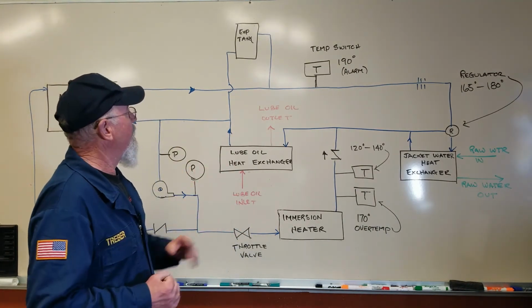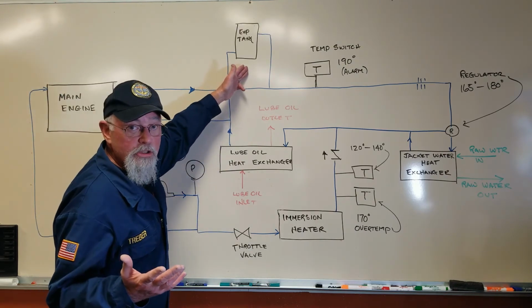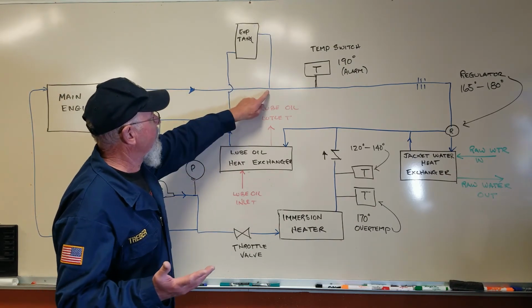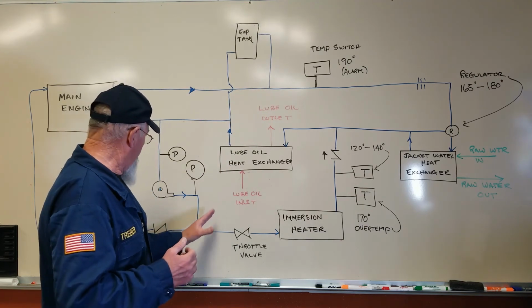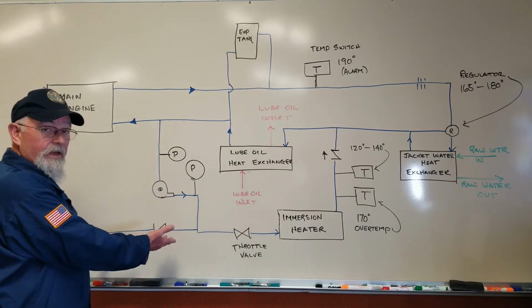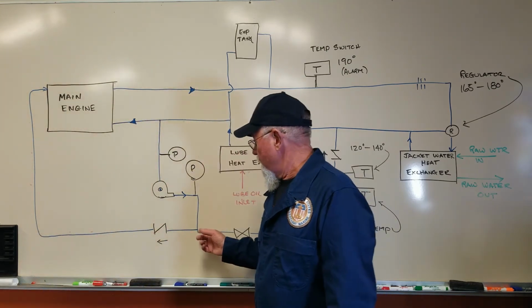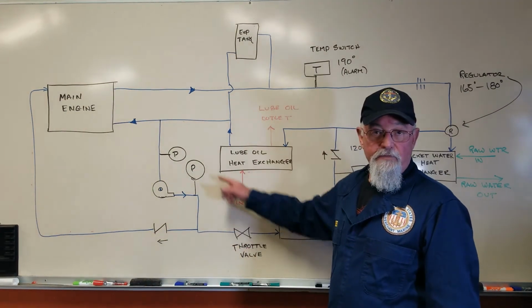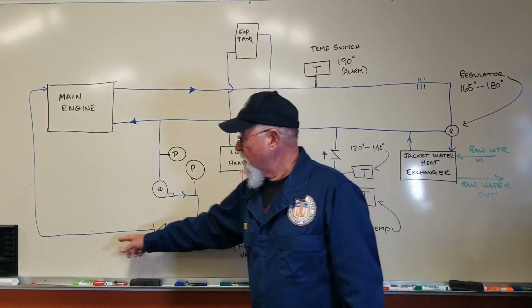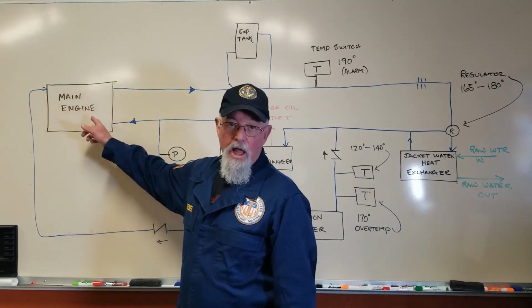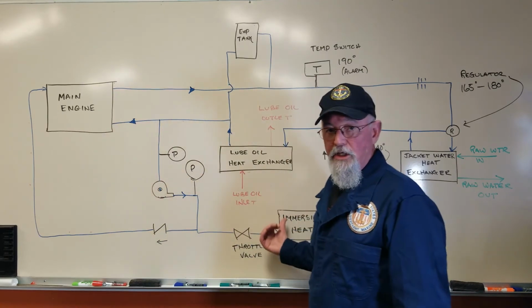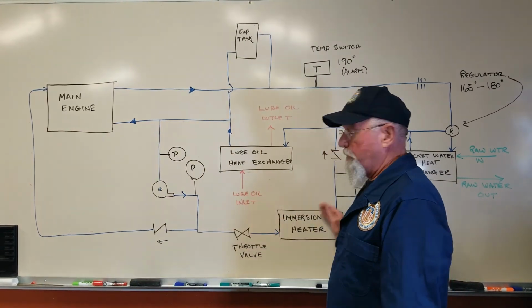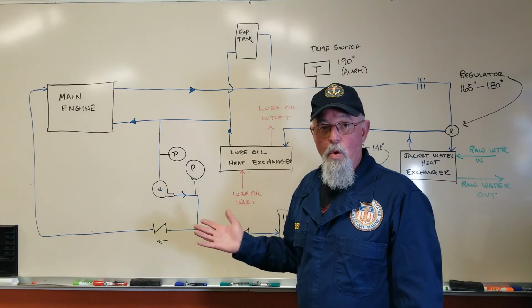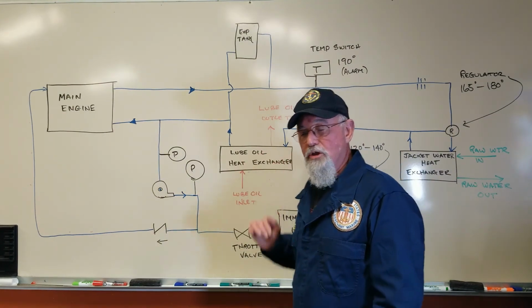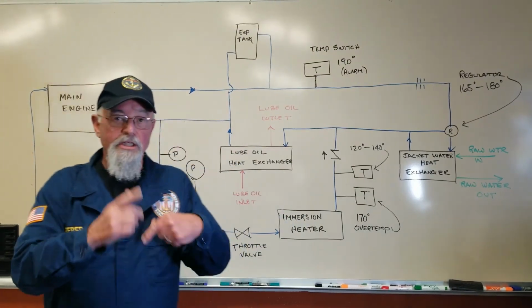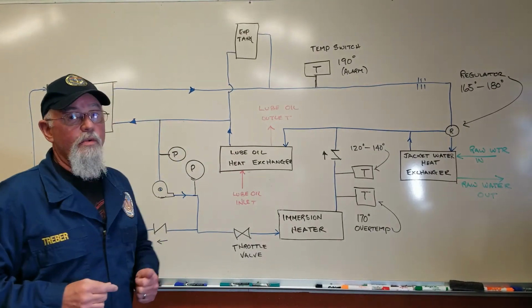So once again, oh, and then we got the expansion tank. Can't forget the old expansion tank at the top. So that's where this is tied in. So flow path, you can see there's a check valve over here. I don't think I mentioned that yet. Because we're throttling this differential pressure, some of that liquid is constantly going just into the engine block, so it doesn't go through the heat exchanger. We're sending a portion of it through the heat exchanger, warming up the water, transferring that heat from the water to the lube oil, circulating it through the sump, and circulating warmer jacket water through the engine block.